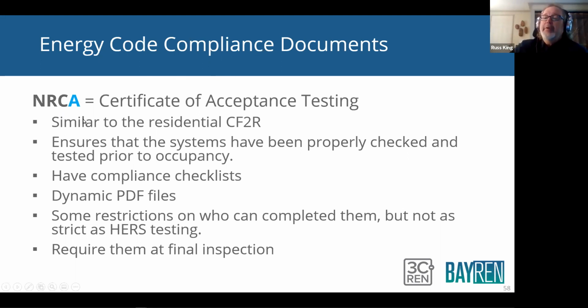So those are important, and it's important for the field inspector to ask for those forms before they file a project. Again, they have compliance checklists, they're dynamic PDF files. There are some restrictions on who can complete them, okay? But not as strict as HERS testing. HERS testing is always third party. With acceptance testing, the installer can actually test their own work, but they have to be certified and trained to do that. Again, require those at final inspection.